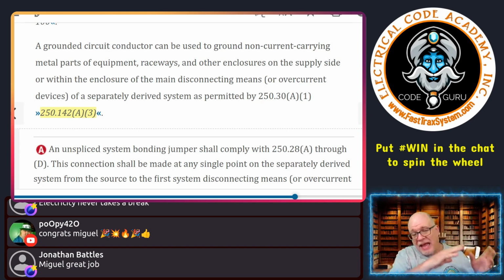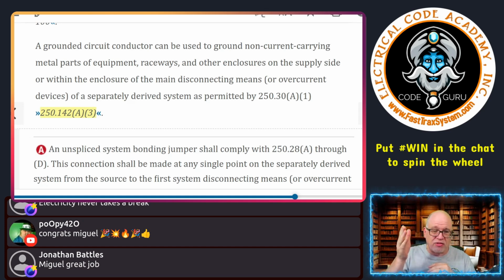So on the supply side, we do that at cabinets and wireways that service conductors are in. We do all this stuff in 250.92. Okay, but not on the load side, except an example here at a transformer where you're allowed to put in what's called a system bonding jumper that would connect X0 to case in that scenario. That is one of the allowances downstream where you're supplying a transformer where you could do that.